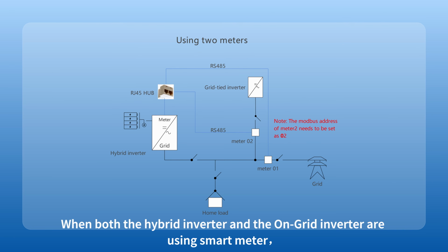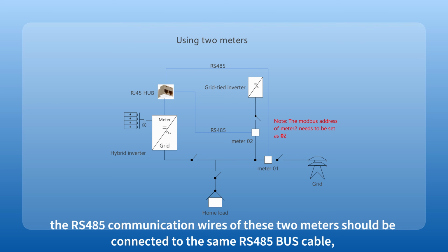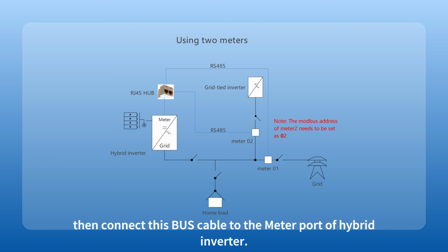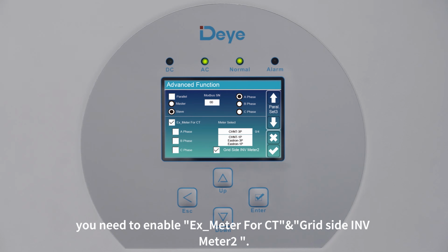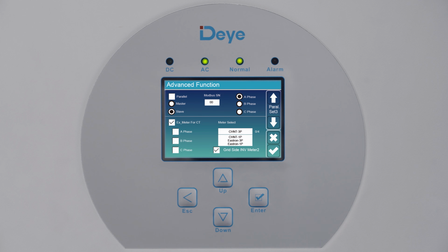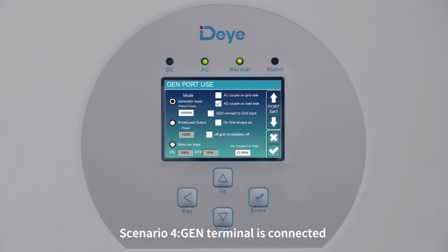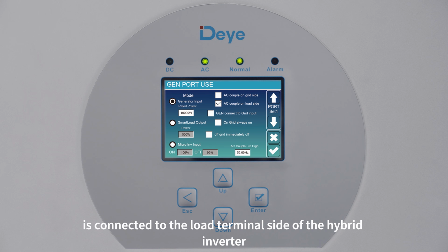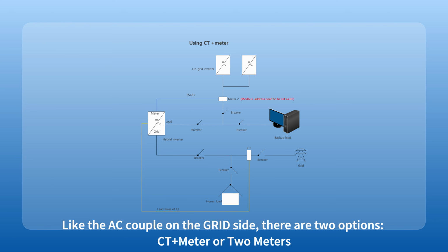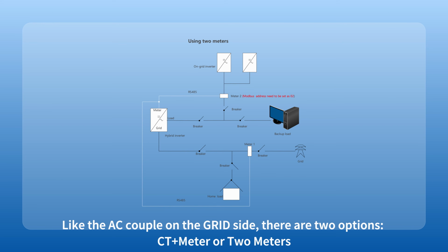When both the hybrid inverter and the on-grid inverter are using smart meters, the RS485 communication wires of these two meters should be connected to the same RS485 bus cable, then connect this bus cable to the meter port of the hybrid inverter. In addition, you need to enable Ex_Meter For CT and Grid Side INV Meter2. Scenario 4. The GEN terminal is connected to the generator or left vacant, and the grid-tied inverter is connected to the load terminal side of the hybrid inverter. Like the AC couple on the grid side, there are two options, CT plus meter or 2 meters.